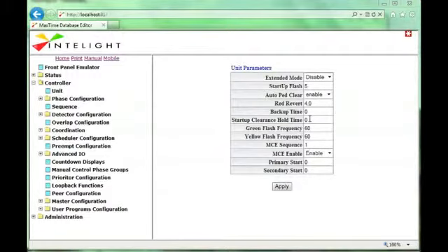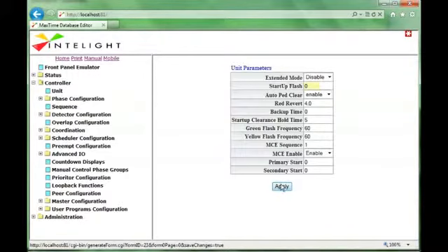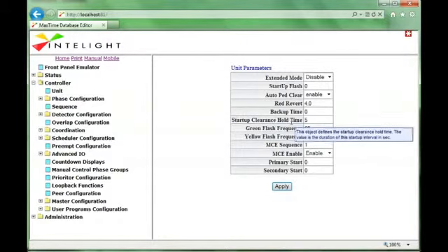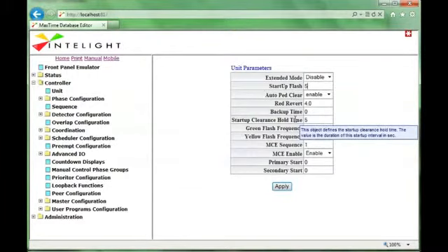Or if I wanted to come up and run 5 seconds of hold, I could zero out the flash and put 5 seconds down here. So I'd power it on, it would be in cabinet flash for the 8 seconds, go directly to all red hold for 5 seconds, and then my startup phases. Or I could do both. I could put 5 seconds in both spots, so I'd have my cabinet flash, my controller flash, and my all red hold. So I can do either, both, or none. I could set zeros in both of these if I so desired, and come directly from cabinet flash to colors.